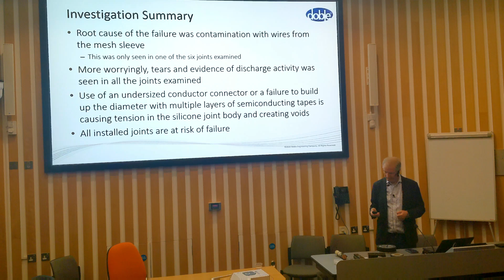So, the reason they were having multiple joint failures was every single joint that they installed had this problem. Every single joint had air gaps, was getting partial discharge, and every joint body we looked at had tears on the inside of the joint tube.